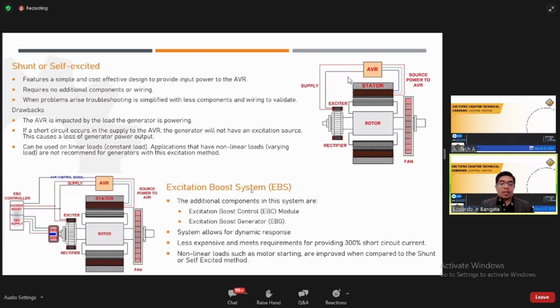However, as you can see in the diagram, you added an additional component, the EBG. It means that your generator will be longer. Now, everybody knows that a standby generator, a backup power, if you are putting it in a building, only a certain space is allocated for backup generators. So this type of generator will be longer, so you have to design the room for your backup generator accordingly.